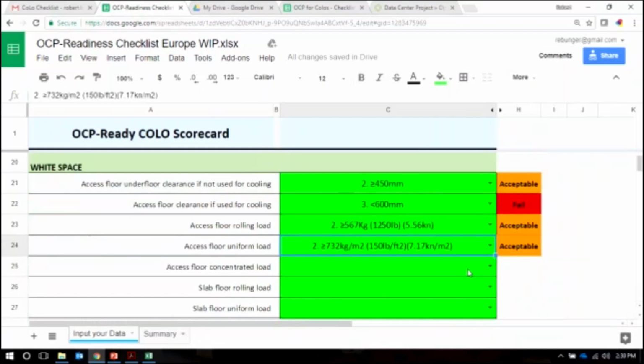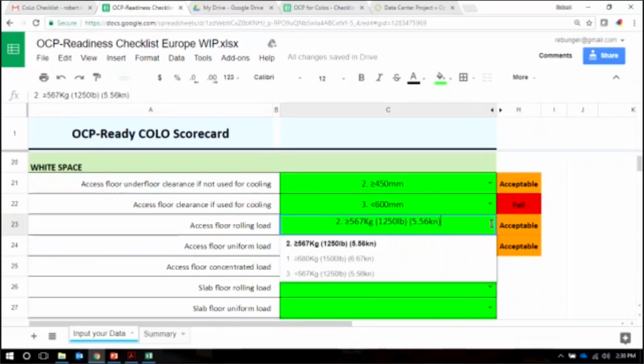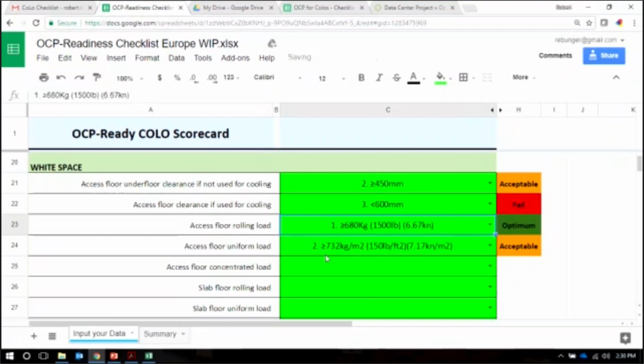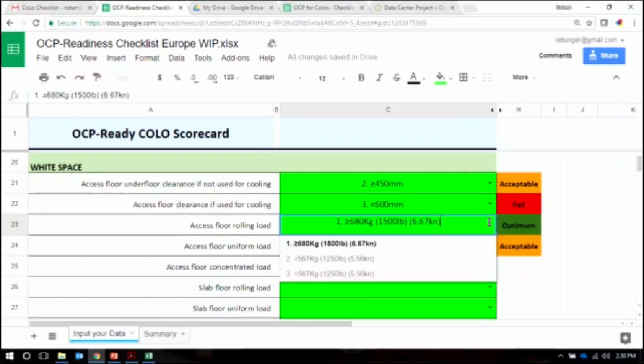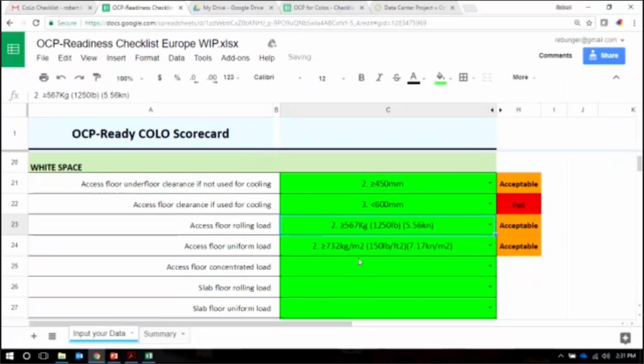Access floor rolling load, so is that the way it's rated? Like how heavy can the thing be that I'm pushing across the floor? Is that how it's rated? So 1,250 pounds seems on the light side for acceptable. I mean, optimum is 1,500. I'm going to check in, I think that's something we've got to look at. It seems light, divided by 4 as well.